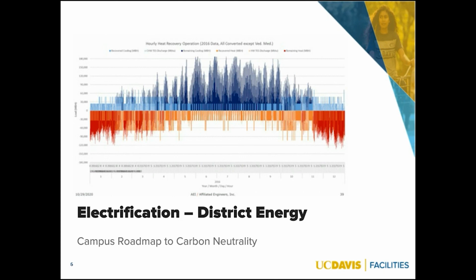The red there right now shows the heating load that we can't do with heat recovery, but the orange and light blue show our heat recovery, or the simultaneous heating and cooling load that we can serve with heat recovery. Chillers are essentially heat pumps at a larger district scale.